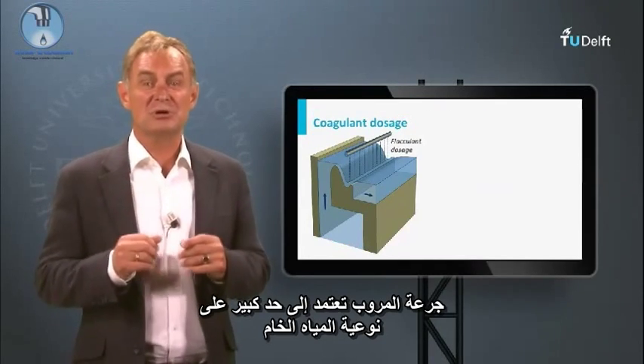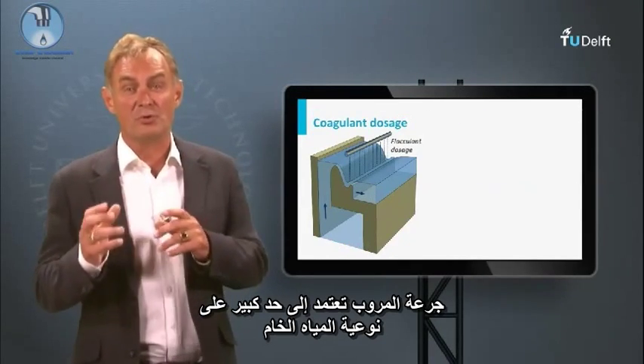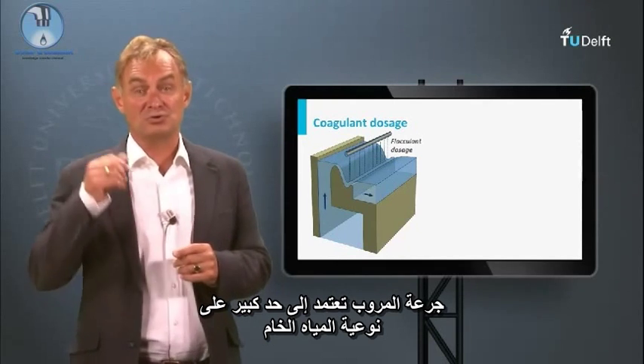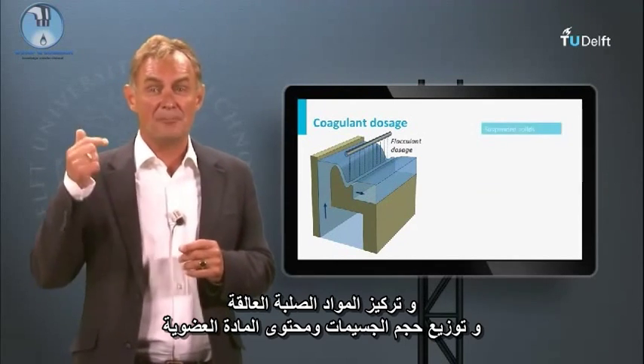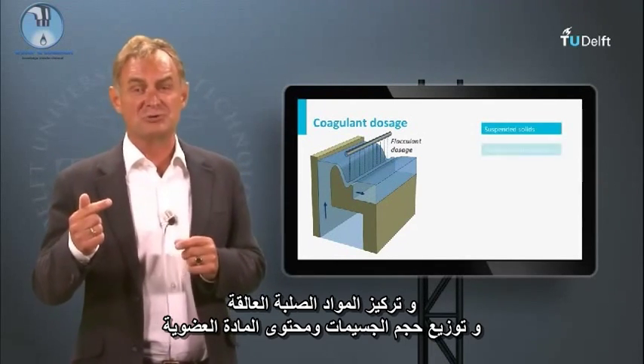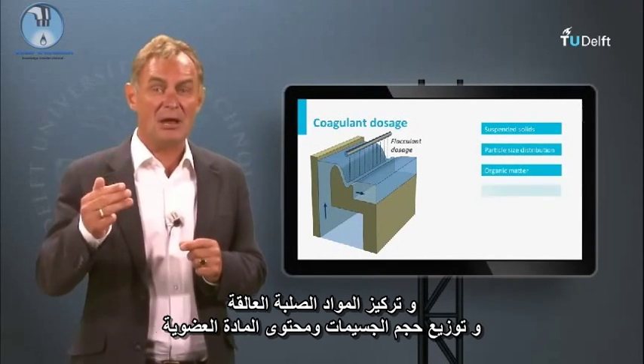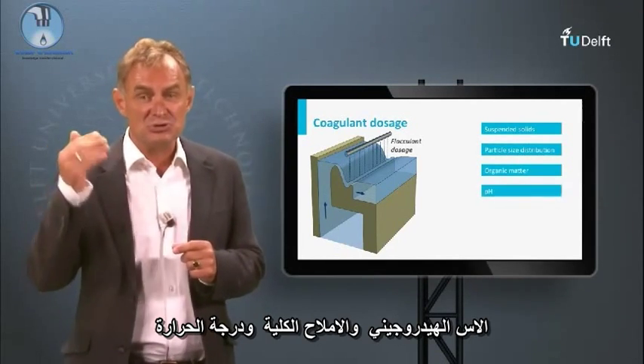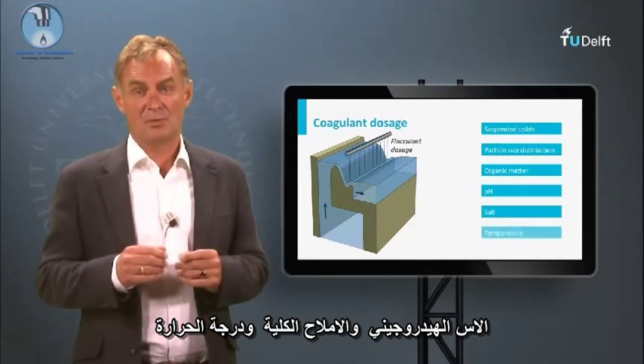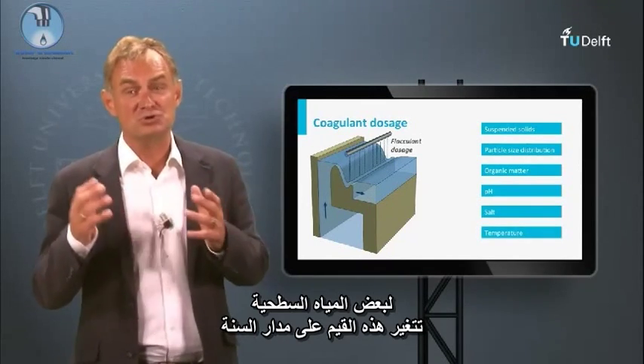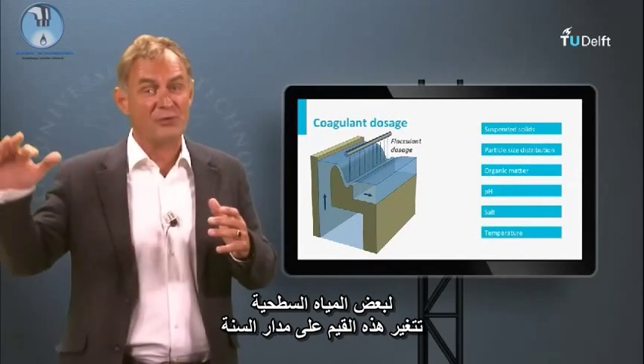Coagulant dosage is largely dependent on the raw water quality: concentration of suspended solids, particle size distribution, organic matter content, pH, salt content, and temperature. For a certain surface water, this varies over the year.